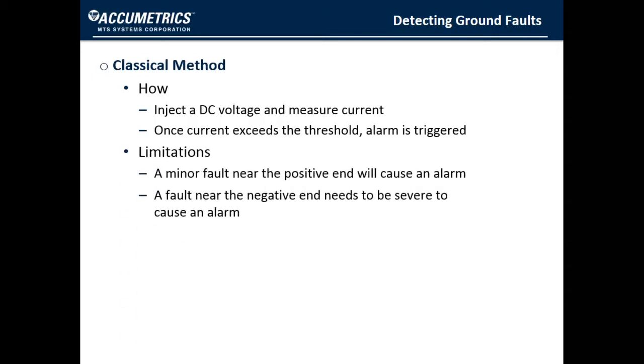This method does have a serious limitation. The resistance threshold that causes an alarm depends on the location of the fault. The detector becomes more sensitive as the location of the fault is closer to the positive end of the field. A severe fault near the negative side may go unnoticed, while a slight fault on the positive side will cause an alarm.